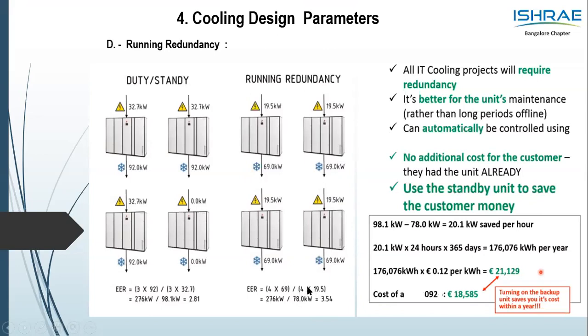If you do the math further, the delta, that is 98.1 minus the 78, the kilowatt is close to 20, and the running hours, if you calculate 20 into 24 by 7 into the rupees per kilowatt of 8, here it is taken in euro, you would recover the cost of the standby unit within a year and a half if you do this math by running the 4 units in a partial load of 75%.